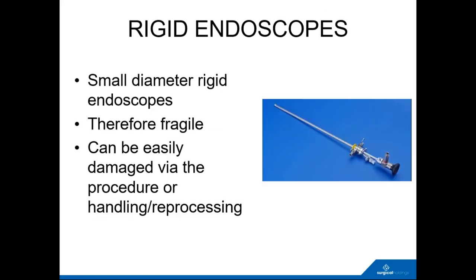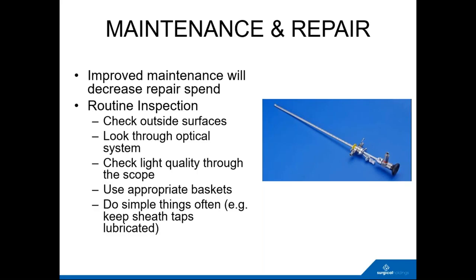So to summarize, rigid instruments are generally small diameter. Probably the biggest instrument I've just listed would be a 10mm laparoscope, but laparoscopes usually will be 5mm now, 5.5. They're therefore fragile. So we're really talking 2, 3, 4, 5mm instruments, and they can be easily damaged either during the procedure or via handling and reprocessing. So, to talk about maintenance and repair, improved maintenance will decrease your repair spend, for sure.